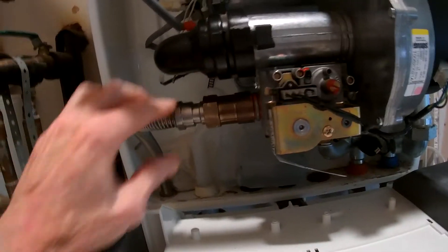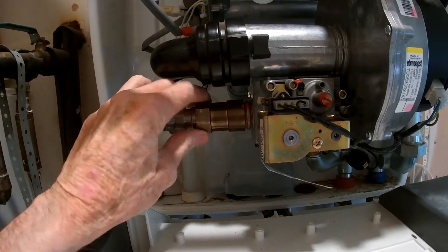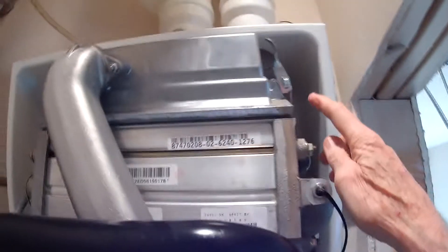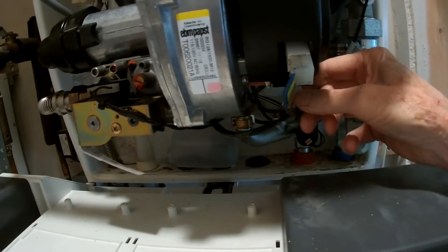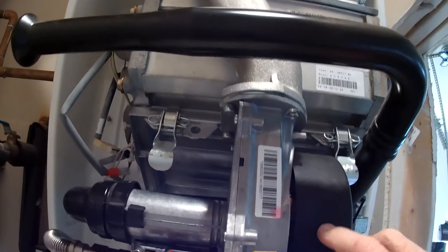You turn everything off. Turn the valve for the gas. See it right down there, green. Turn that off so you don't have any gas flow. The next thing you do is take the gas line off, which is right here. This is supposed to be finger tight. Mine was not. Had to use a wrench on it. But you take that off. Then you disconnect this latch and this latch, and then this connector, this connector, and this connector. Then you'll be able to lift this off, this whole unit off.